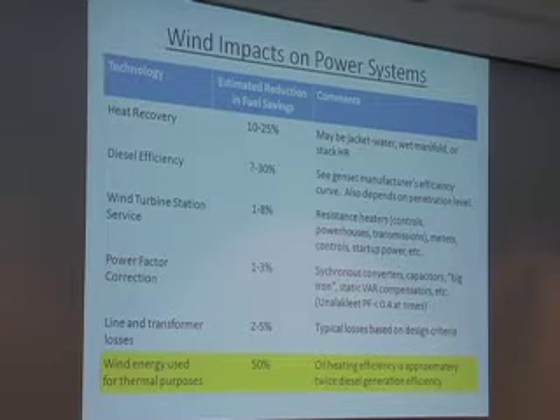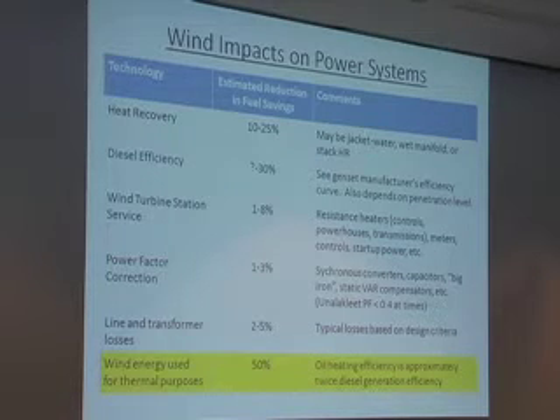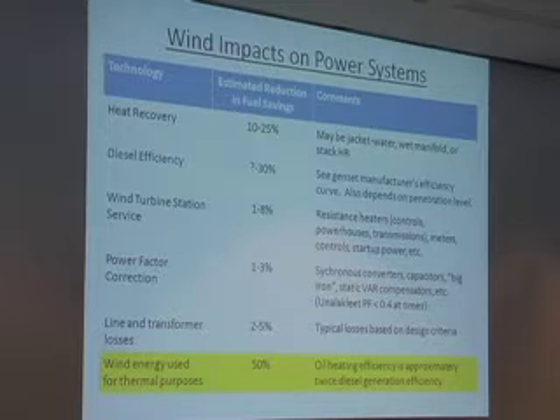So to start off with, heat recovery. It might sound like a really old idea, maybe something that's not changing very fast, but I'll show you some of the applications that we're working on. Alan's taking the lead on some of these. They're changing pretty fast. Traditional jacket water heat recovery from a diesel has an impact on estimated fuel savings of wind turbines of approximately 10%. So that's the low end of the range you see there. And that's often providing heat to a school or some load like that that's seasonal as well.